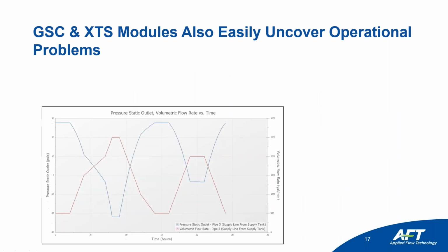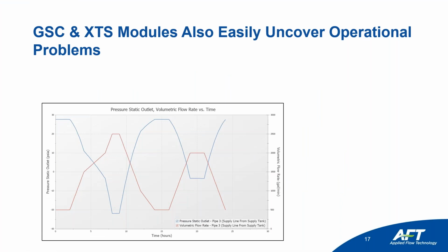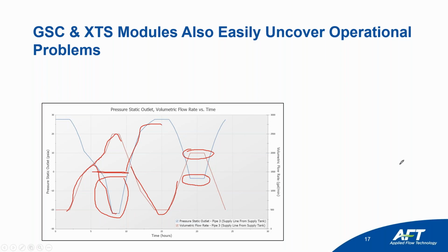So I just want to highlight the overall results. When I went through this, I noticed that my pressures were dropping below my vapor pressure at a certain time. So the blue line, that's the pressure at that assigned flow junction. So what you can see here is as the red line, which is your volumetric flow rate, this is your flow profile that you specified, as that flow demand increases, your pressure drops. And it drops below vapor pressure, which is right about here. You are cavitating at this time for several hours. And then you increase your pressure again because the flow drops again. And then later on in the day, you have another increase in flow rate, so you have another associated drop in pressure. You're cavitating again.